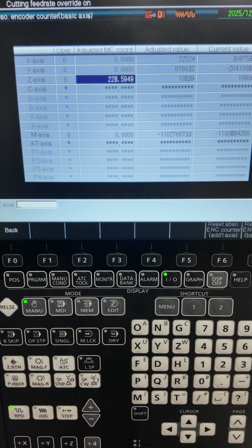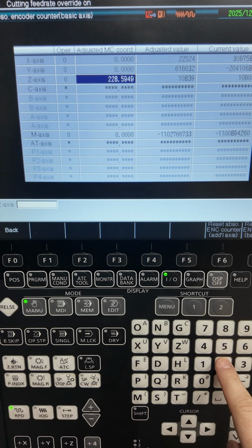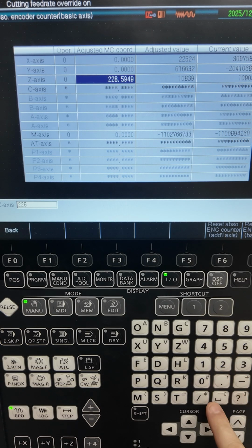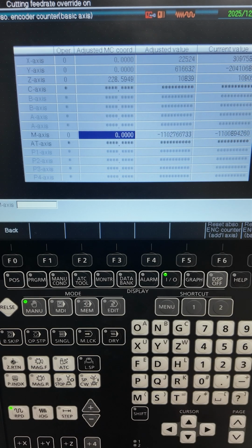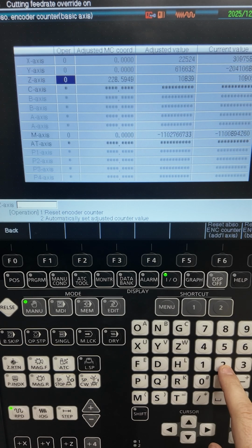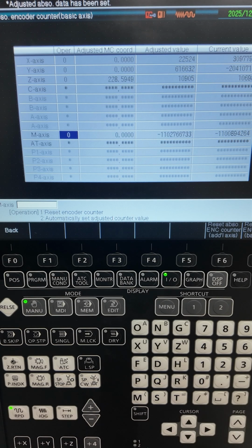So in this case, it's 2.9998 inches plus a 6-inch gauge block stack. Converted to millimeters is 228.5949. Which is what is already in there, but I'll just type it in anyway in case it's a different value. And then you go over here and you type only in this one, you hit 2, enter. You should hear a click and see it go right back to 0, and now your encoder is calibrated for Z.